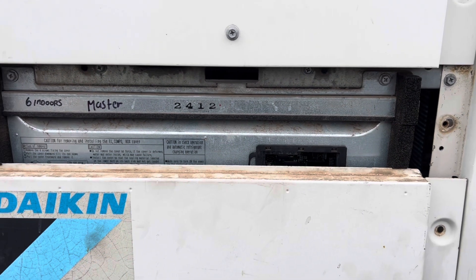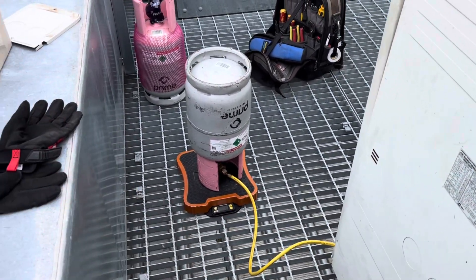Just come out of test mode, looks like everything's sweet. What I'm going to do now is go down and get the service tool, plug in, and get the remaining charge in. Just connecting to the system now. I'm going to get the rest of the gas in this system, then get it to run on its own accord. Once all the gas is in, I want to start recording data so I can have a look at it - see if we can spot any standout issues, or I can take the data away and go over it as well.